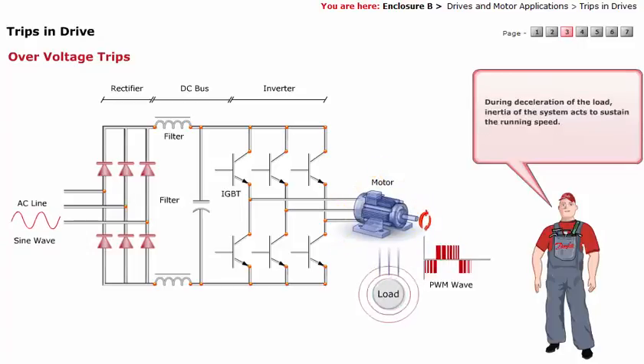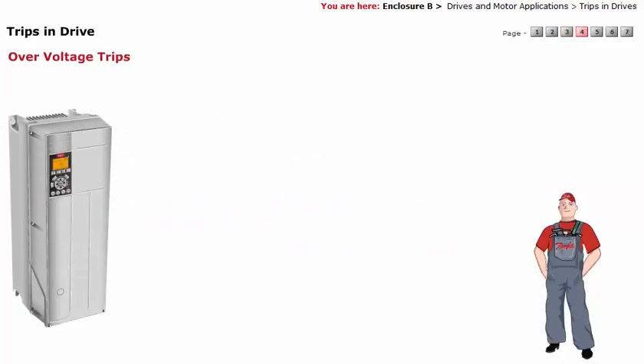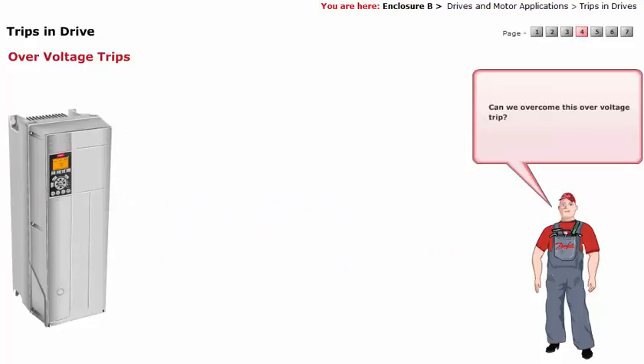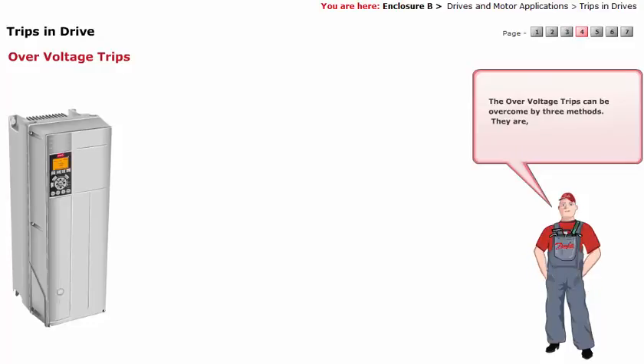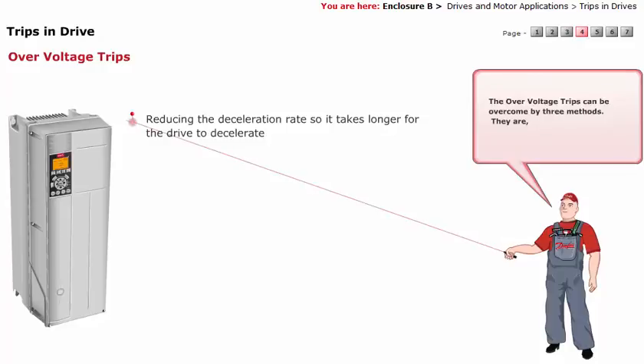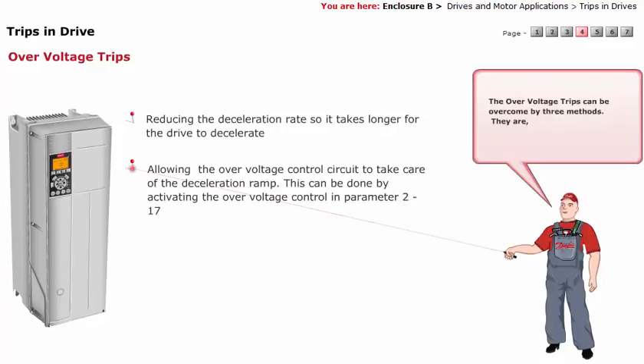The over-voltage trips can be overcome by three methods. First, reducing the deceleration rate so it takes longer for the drive to decelerate. Second, allowing the over-voltage control circuit to take care of the deceleration ramp — this can be done by activating the over-voltage control in parameter 2-17. Third, installing a brake resistor on the unit across the DC bus.